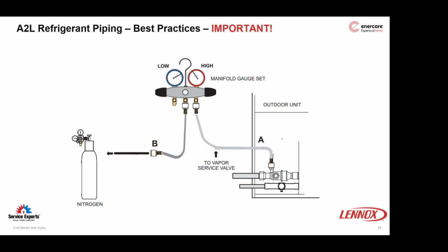So we had to have a dedicated gauge set for our pressure testing. Our dedicated pressure gauge set didn't have a low side gauge. It had two high side gauges, and it had to be shown as nitrogen only, pressure test only gauges. It could not be used on any other refrigeration system. And once the pressure test was over, we had to switch our gauge hose system, our gauge manifold set, over for evacuation. So anytime we were communicating with refrigerant, those pressure test gauges couldn't be on.